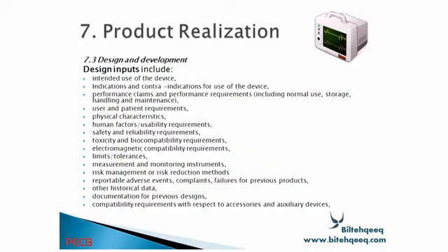And design input includes intended use of the device, indications and contraindications for use of the device, performance claims and performance requirements including normal use, storage, handling and maintenance, user and patient requirements, physical characteristics, human factors, usability requirements, safety and reliability requirements, toxicity and biocompatibility requirements, electromagnetic compatibility requirements, limits, tolerances, measurements and monitoring instruments, risk management or risk reduction methods, reportable adverse events, complaints, failures of previous products, other historical data, documentation for previous design, compatibility requirements with respect to accessories and auxiliary devices.